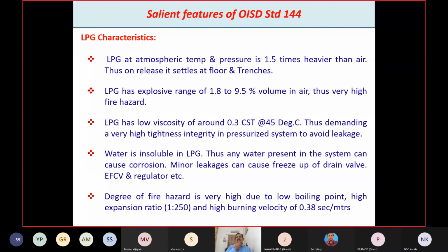So now let's see the salient features of OISD standard 144. This is exclusively developed for LPG, liquefied petroleum gas. So you should know the characteristics of LPG. LPG at atmospheric temperature and pressure is 1.5 times heavier than air, so it tends to settle down at floor level. That is why the gas sensors are fixed 1 foot above the ground level. And LPG has a flammable range of 1.8 to 9.5%. The LEL is 1.8% and the UEL is 9.5%. That's a very high fire hazard.